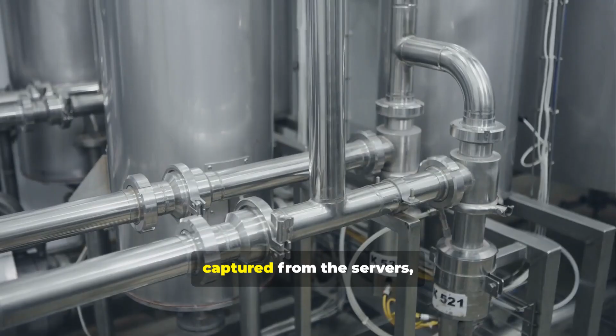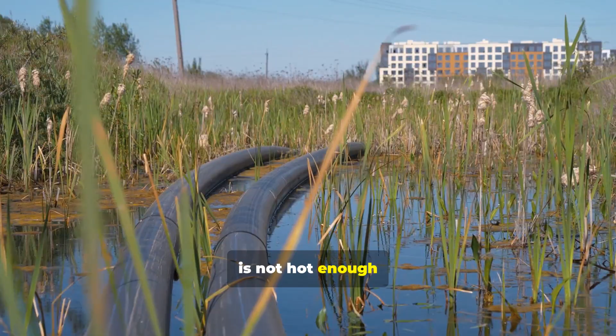Engineering focuses on maximizing recovered heat while minimizing energy use. Liquid cooling over air cooling captures heat in a denser, manageable medium. The entire layout is optimized: the arrangement of the server racks, the design of the plumbing. The server is no longer just a computer. It is the furnace at the heart of a larger energy system. And the first step is to capture every degree of its warmth. The warm water captured from the servers, while containing a significant amount of energy, is not hot enough to be useful for Finland's district heating systems.